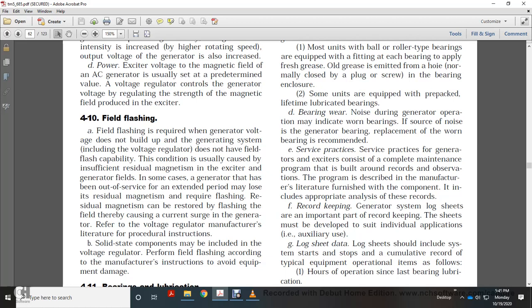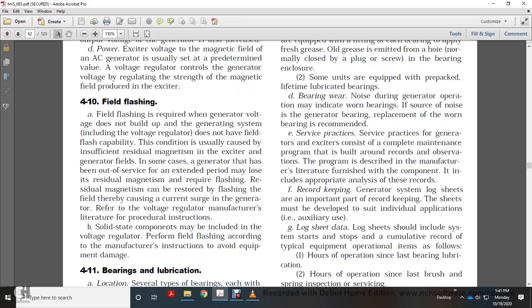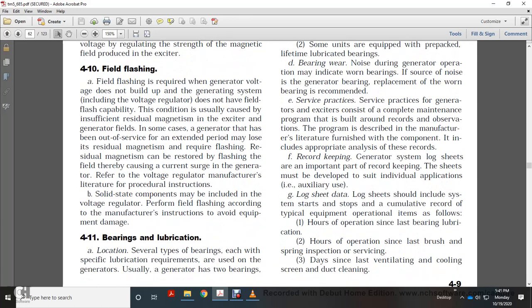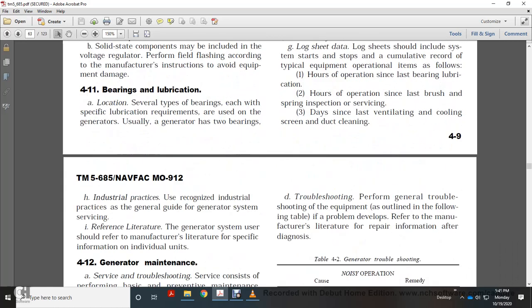This includes the proper analysis of these records, keeping the generator system log sheet. It's important that the record keeping sheet be developed for the individual application and auxiliary use. Log sheets should include system startup and stop, the cumulative record, the type of equipment and operation itself. Also set a cumulative record of repetitive equipment operation items, filed with the hours: when the bearing was last lubricated, the brushes last serviced, the bearing inspection service, and the station's last venting and cooling screen and duct cleaning.